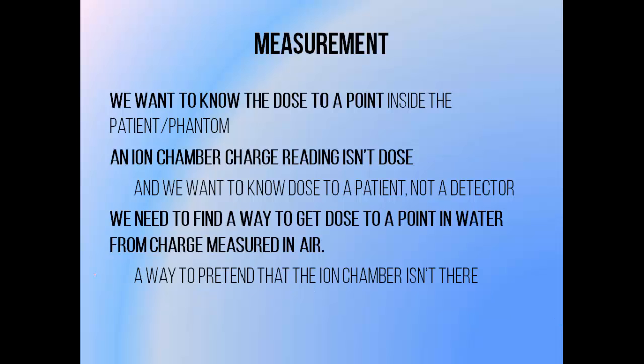There are a few key problems that we need to solve if we want to use an ionization chamber to measure dose to water. What we want to know is dose to a point in a water phantom, but what we can actually measure is charge generated in an ionization chamber volume close to this point.